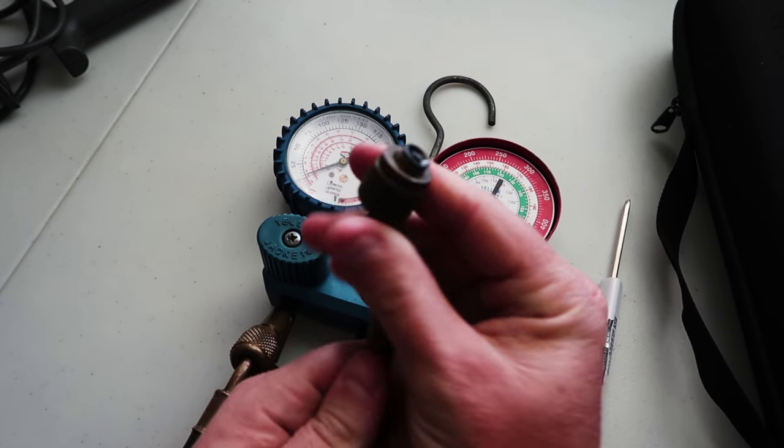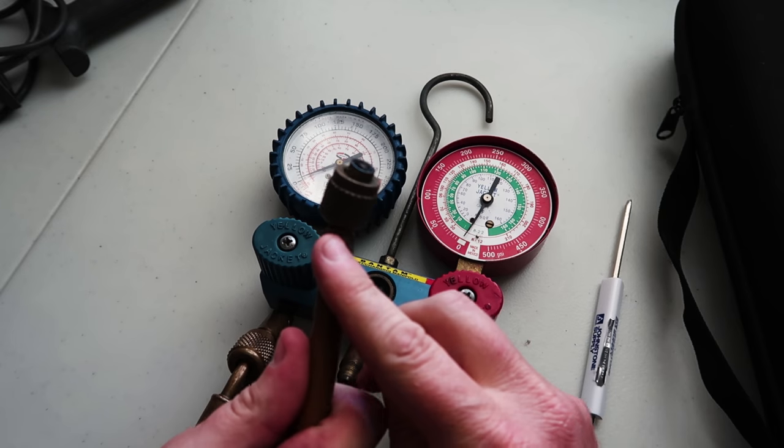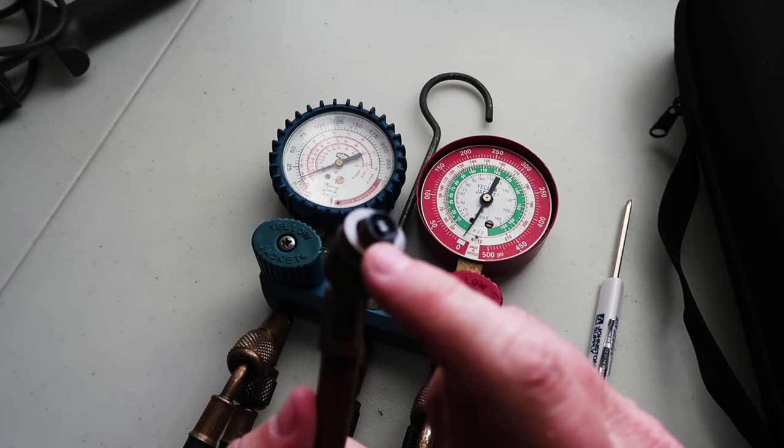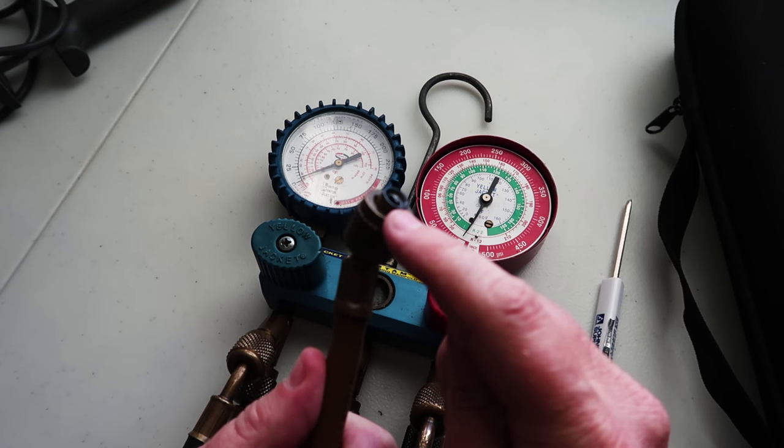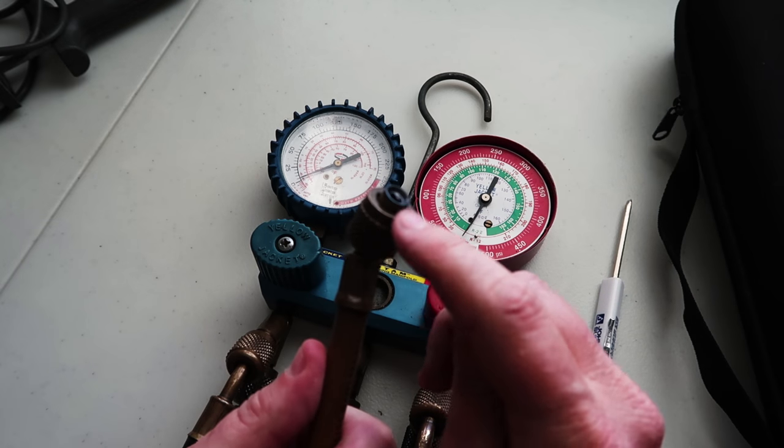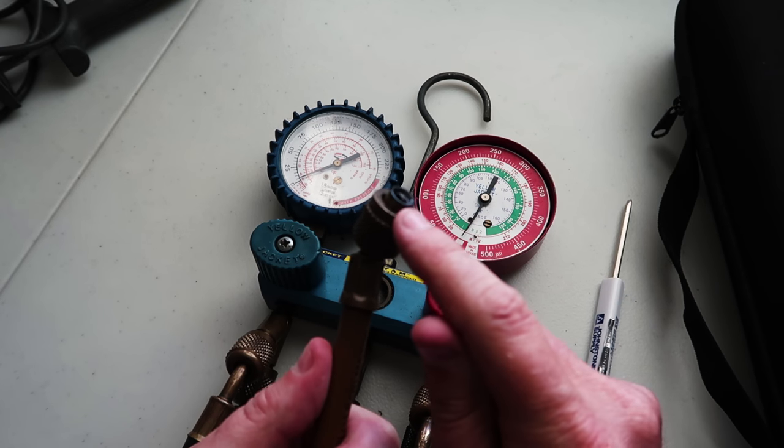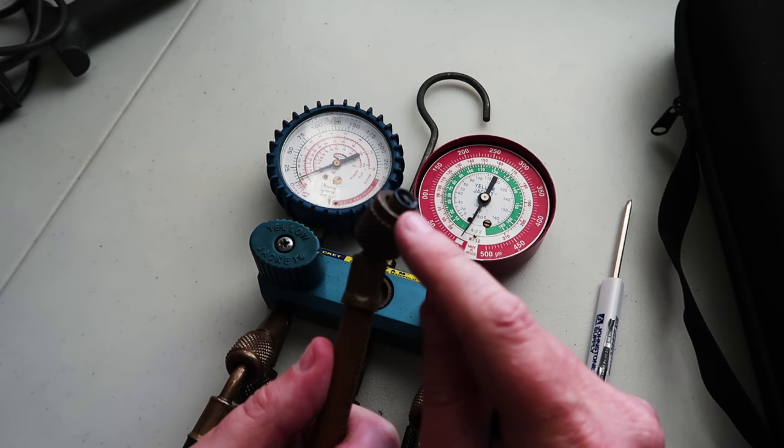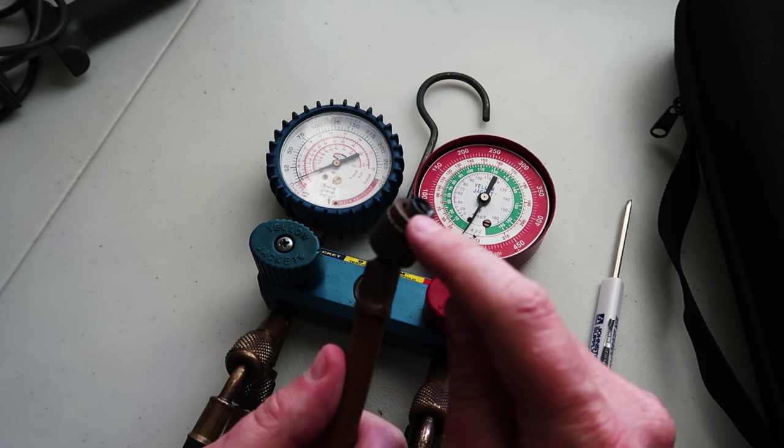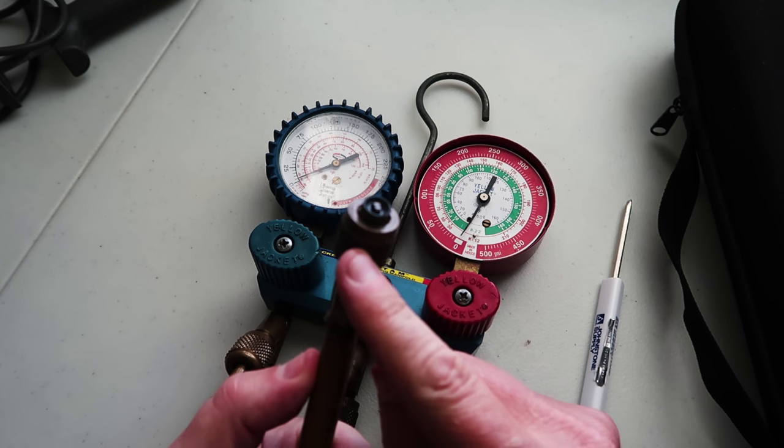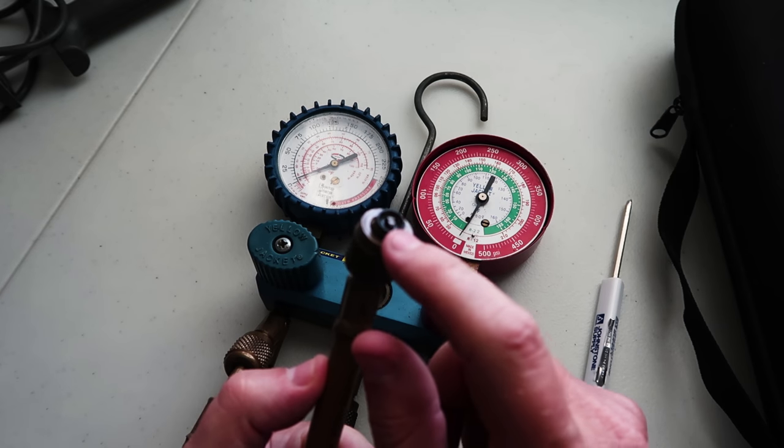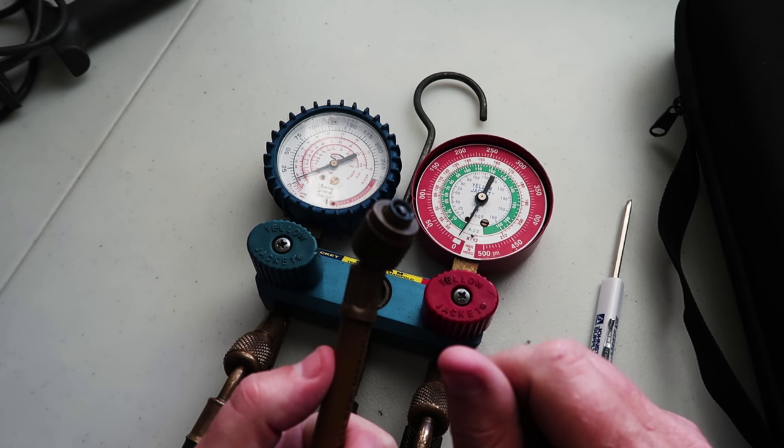The same thing is true when you attach these onto the system. You don't want to over tighten them because you'll over compress the seals inside here, and you'll notice that you have to replace your seals more often. Be very thoughtful about the seals in your equipment. Also don't overheat these. So if you're brazing on a system, you want to make sure to keep the valves cool so you don't overheat the rubber seals inside. Otherwise, you're going to find that you go through a lot of these seals. And on most gauges, these are replaceable.